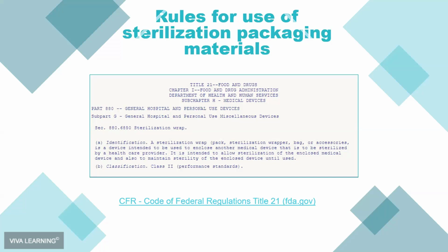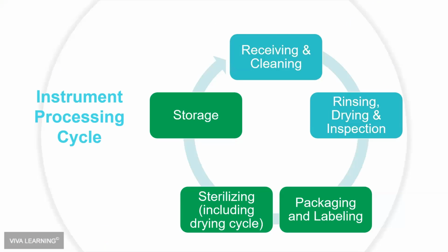Or can I just use a paper bag to put my instruments in to go through the sterilizer? And the answer is no. You need to use something that's cleared by the FDA for use as sterilization packaging material. So now that we have the regulatory stuff out of the way, let's talk about the instrument processing cycle.